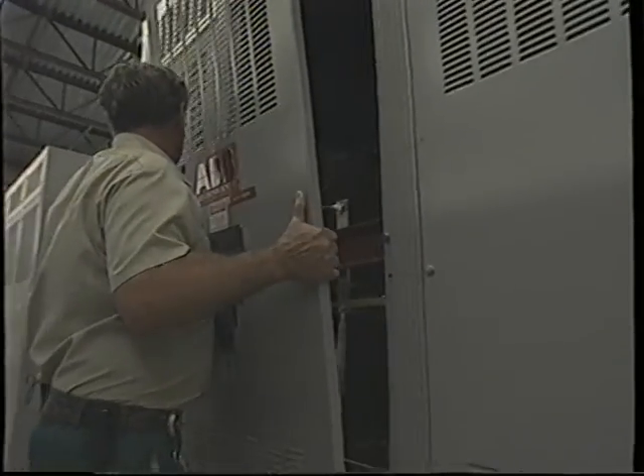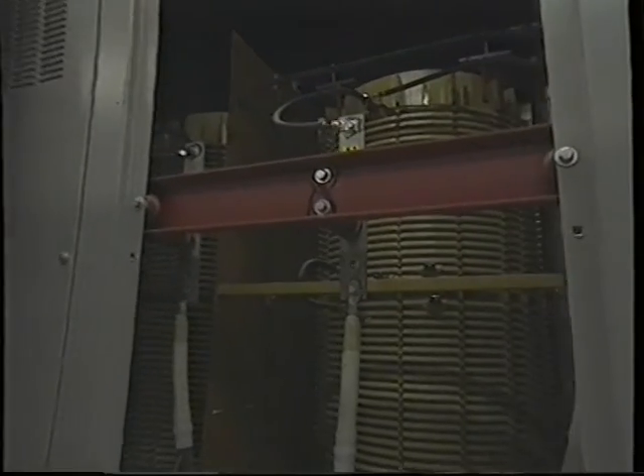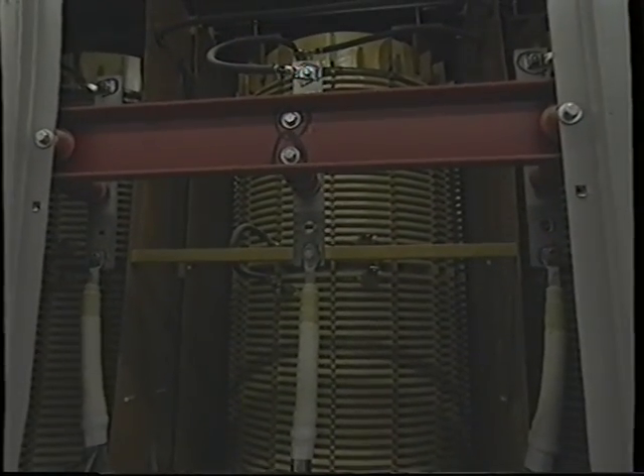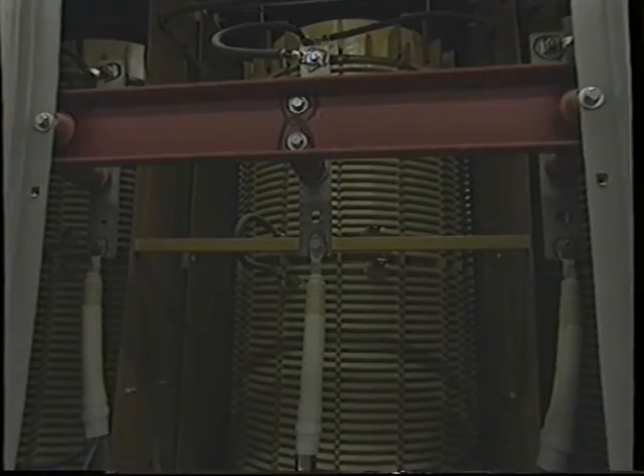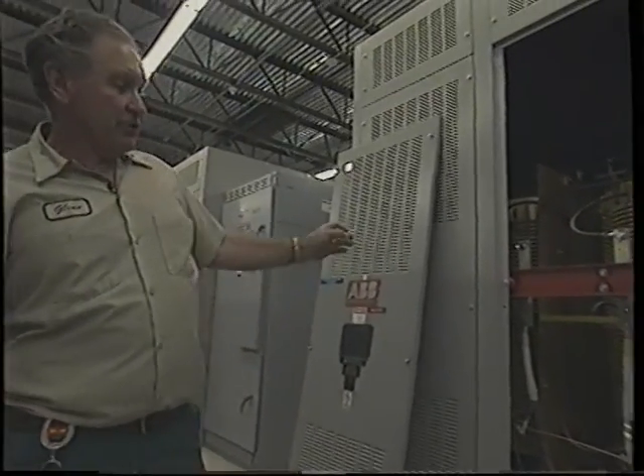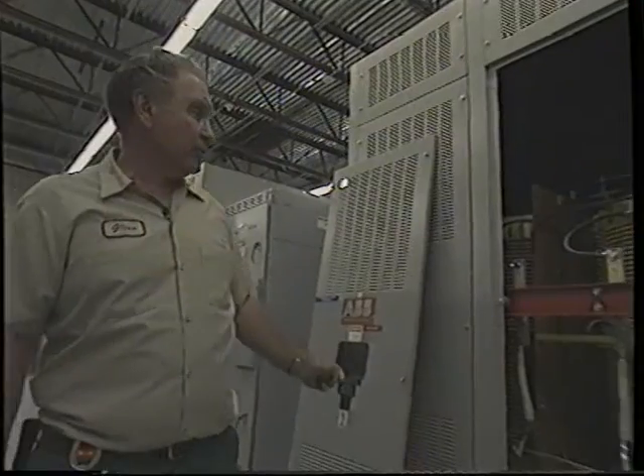The Luxor Hotel needs its own bank of transformers to step the high voltage alternating current down to various voltages. Okay, you're seeing 3 big coils in there. That reduces the 12,400 volts down to 4,160 volts. This is the power that we use for our air conditioning units. And then it goes to another bank of transformers that breaks it down to 120/208 volts that we use for lighting and for slot machines, gaming, and whatever else it might be.